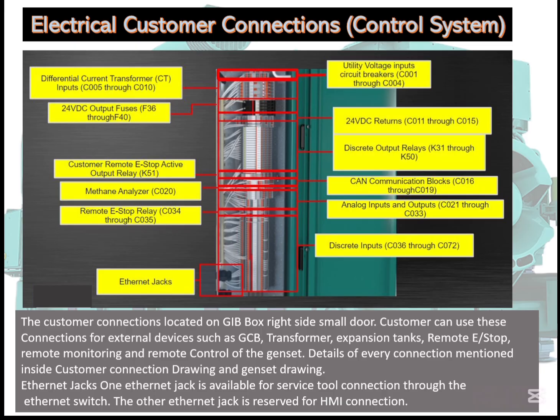We have inputs: remote start, remote stop, load demand start, customer faults, then fire protection, differential fault, DCB trip, utility DCB trip, DCB position. All those inputs are labeled C036 to C072. Then we also have the Ethernet connectors where we can connect our service tools.